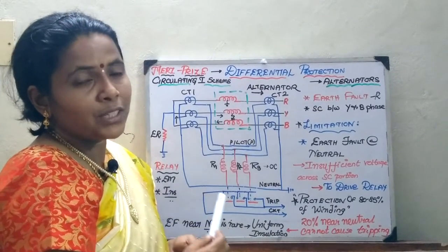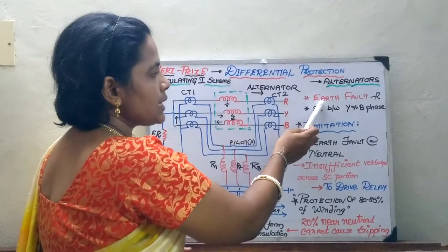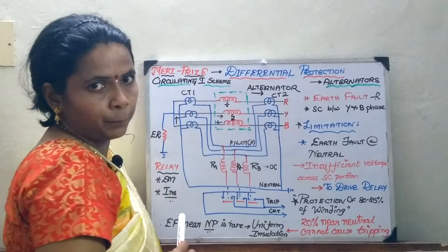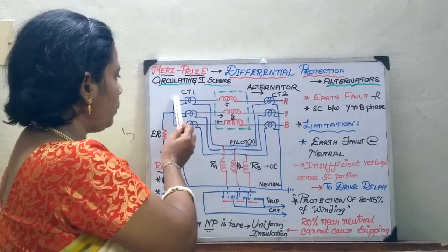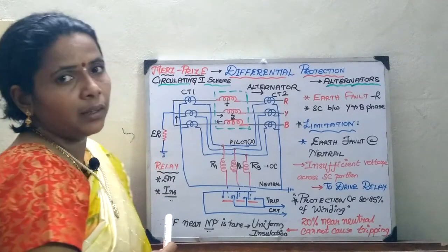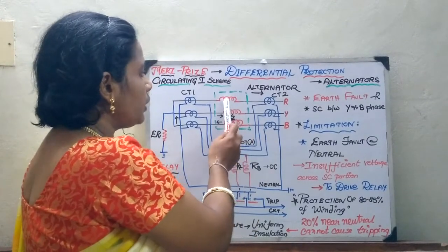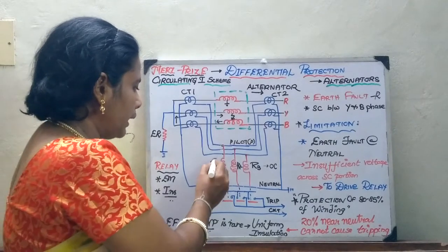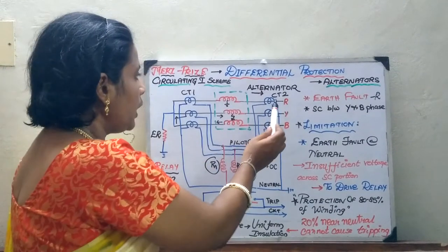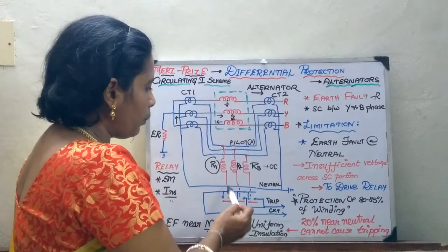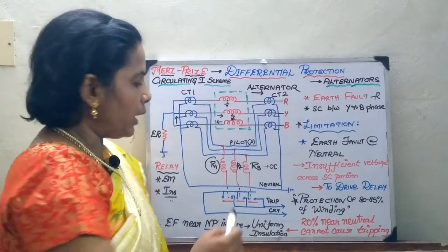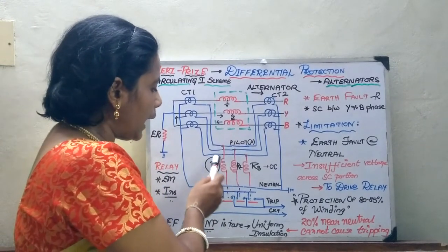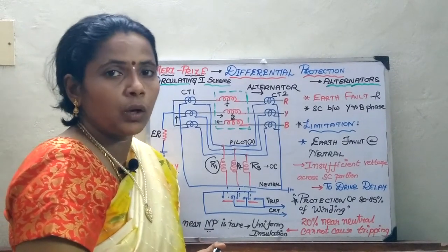Now let us analyze performance when a fault occurs. Consider an earth fault occurring at the R phase. When the fault occurs, current passes through the earthing resistance and gets grounded, resulting in an imbalance in the current through relay R1. The current path goes via the neutral point and the R phase pilot cable, and this unbalanced differential current is detected by relay R1.